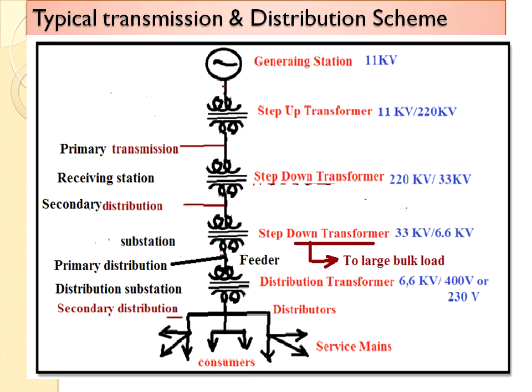It consists of a number of 3-phase AC alternators working in parallel as per the capacity of the station. The generated electrical power is boosted from 11 kV to 220 kV, because we have to transmit the electrical power with high voltage. It gives an economic design. Hence we have to go for high voltage as much as possible within limitations.